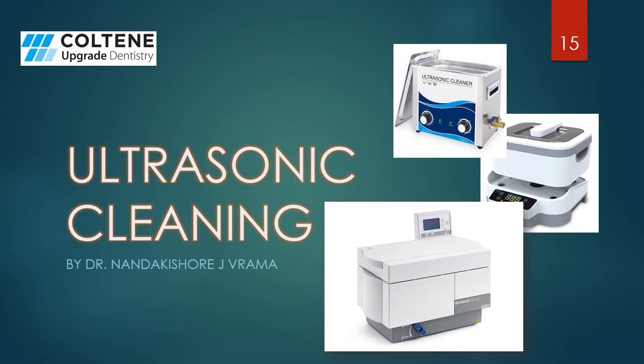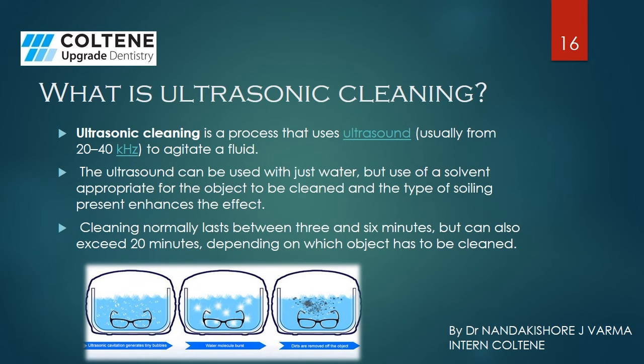Let's see in detail about ultrasonic cleaning. What is ultrasonic cleaning? It is a process that uses ultrasound to agitate a fluid. The ultrasound can be used with just water, but use of a solvent appropriate for the object to be cleaned and the type of soiling present enhances the effect. Cleaning normally lasts between 3 to 6 minutes, but can also exceed 20 minutes depending on which object has to be cleaned.